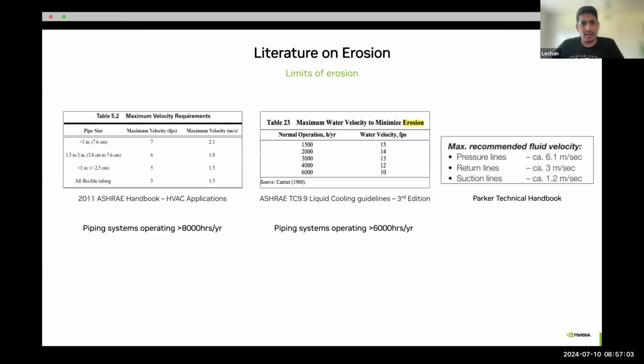From a different source, Parker, a manufacturer of hoses, they said we can go up to 6.1 meters per second in a hose, and that for pressurized pipelines we can go up to 6.1 meters per second, and that would be the maximum velocity limit to see the EPDM hoses are safe from eroding.